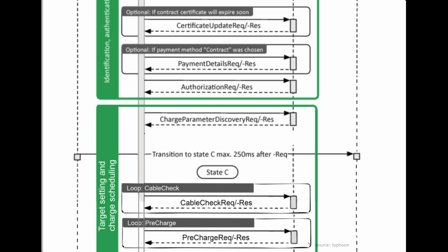6. Contract Authentication. If the EV uses a contract, authentication is performed to ensure the credentials are valid. Optional steps include certificate installation or updates if required. Finally, we have the Charge Parameter Discovery Request/Response, where the EV sends its charging parameters, like Vmax, Imax, and Pmax. The EVSE responds with its own limits, ensuring both systems are synchronized. Once all parameters are agreed upon, the EV transitions to State C for charging.